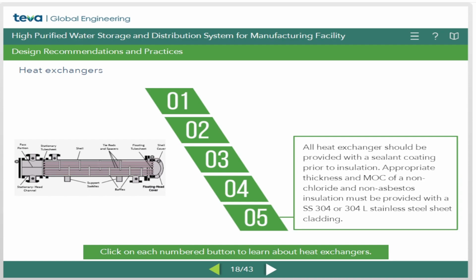All heat exchangers should be provided with a sealant coating prior to insulation. Appropriate thickness and MOC of a non-chloride and non-asbestos insulation must be provided with a SS304 or 304L stainless steel sheet cladding.